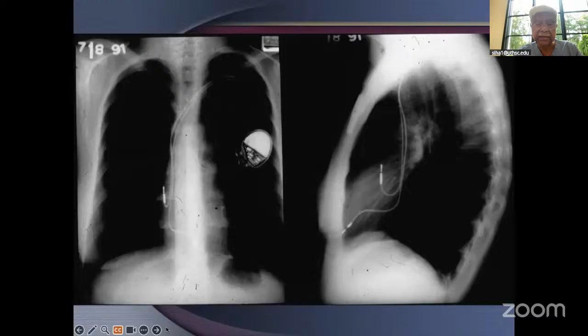The pacemaker mode. Normally you'll ask, what is VVI, what is DDD pacemaker? To understand, predict, and troubleshoot the pacemaker behavior, it is critical to understand the pacemaker timing and the pacemaker modes. The pacemaker mode defines, if I say VVI, the first letter defines which chamber is paced. The second letter defines which chamber is sensed. And the third letter defines the response to sensing. If there is a normal QRS complex, it will inhibit the pacemaker, it will be VVI.